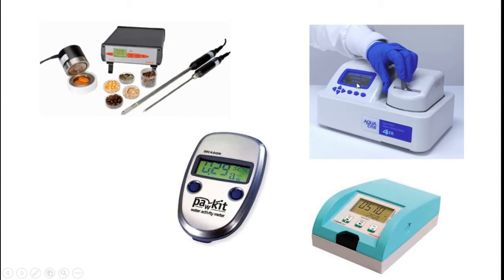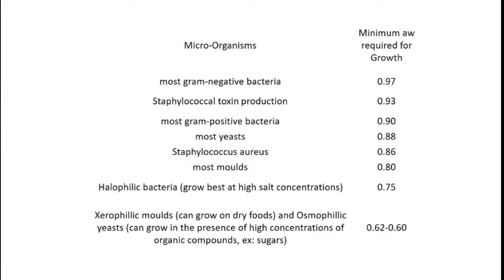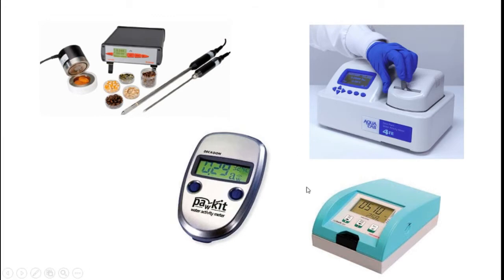You'll notice on this pocket it only has two decimal places where some of these other larger meters are going up to three or in the case of the Aqualab up to four decimal places of accuracy. That said, if we go back to this table, in general within regulatory limits we're seeing them expressed at two decimal points. Take that into consideration when you are purchasing a device because something with less accuracy is going to cost a little bit less, but it may not give you the level of accuracy and control that you need.